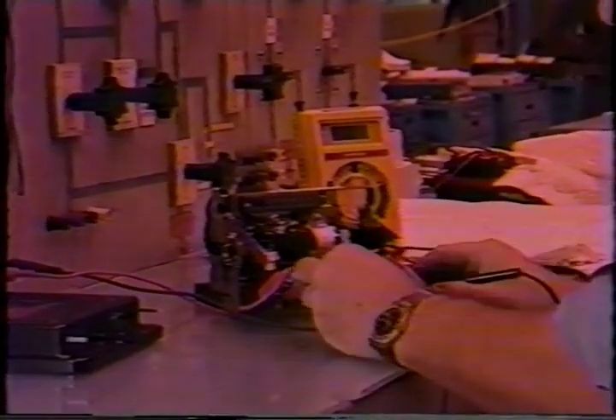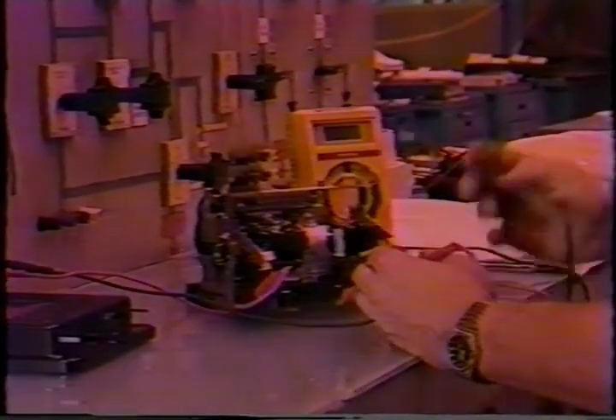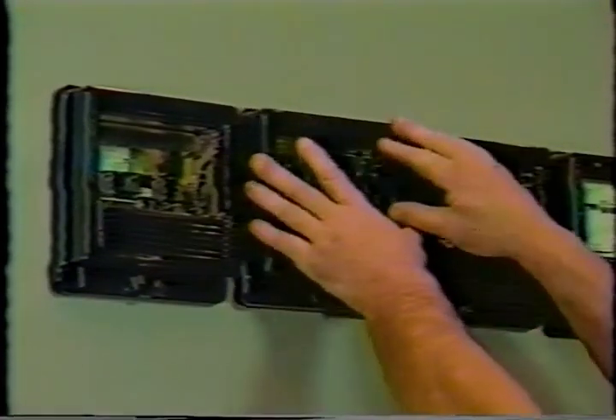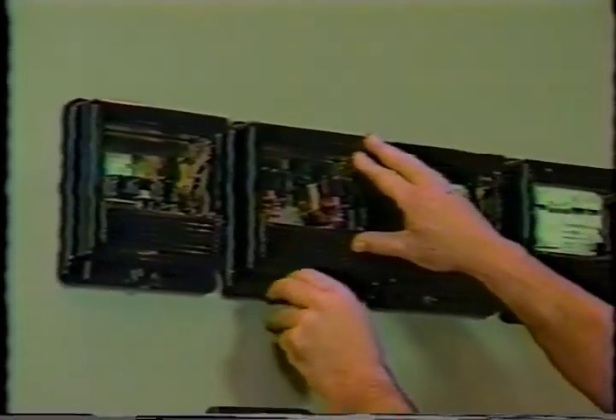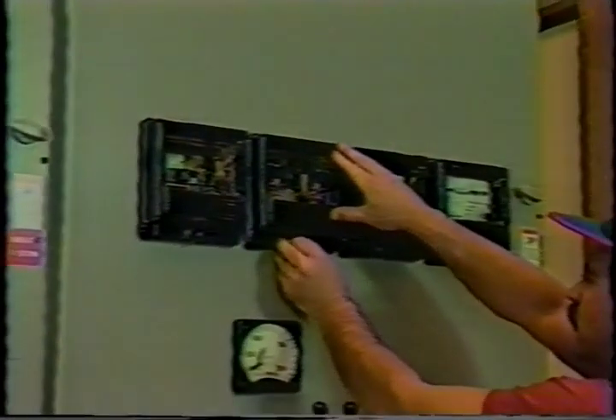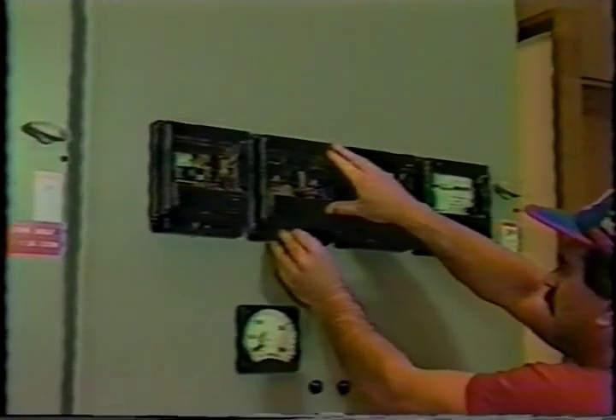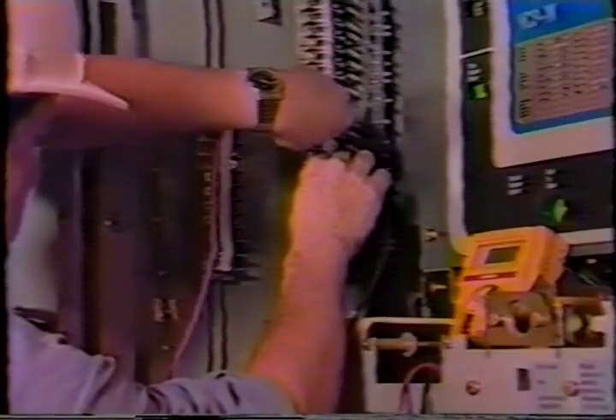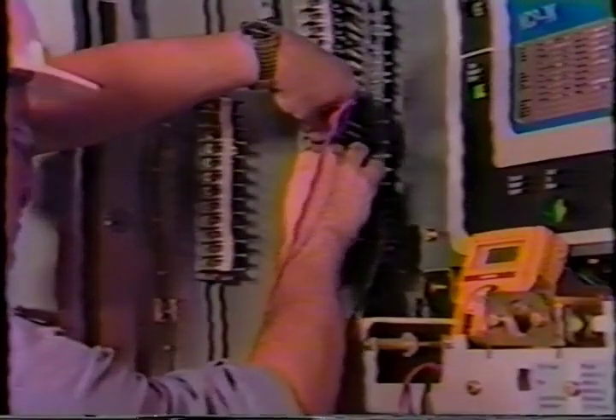Coordinate the settings of the relays with the apparatus and other protective devices on the system. If the covers are removed from meters, relays, or other devices for installation or test, handle them carefully. Replace the covers as soon as possible to keep out dust and dirt. Perform a load check of the control circuits.